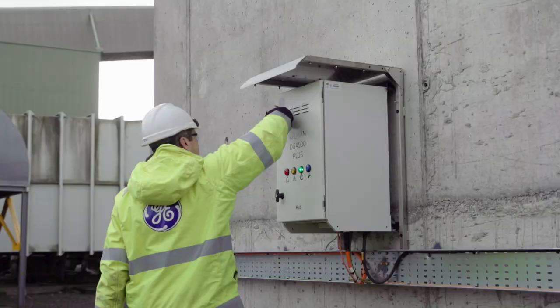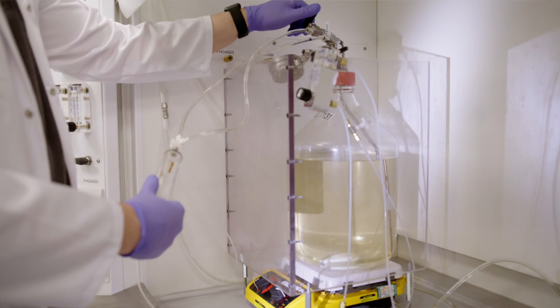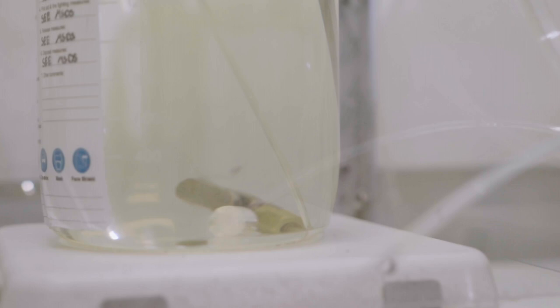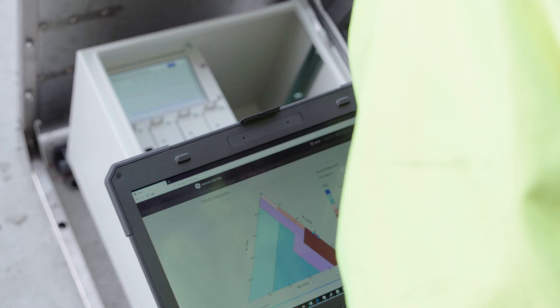Yeah, really great example with the products that we have here, the DTA 900. For example, we have a feature that the team developed within the last couple of years, which is really looking at our customer needs, where they want the best and fastest response for something that's happening in the substation transformer. So as you'll know, we measure the gases that are in the oil. For our customers, it's really important. If something is happening, they want to know quickly. So we've developed some new features which allow us to do a measurement as fast as about 30 minutes. Now that's market leading. You can take a sample from the transformer, take it into one of our gas analyzers and make an assessment very quickly.